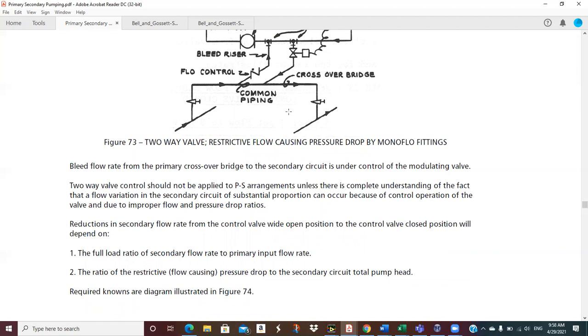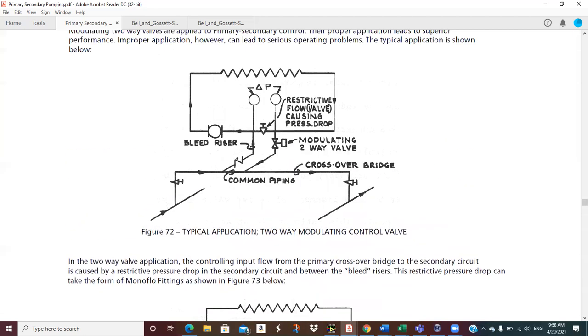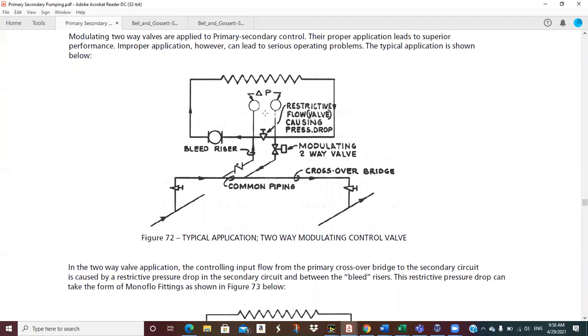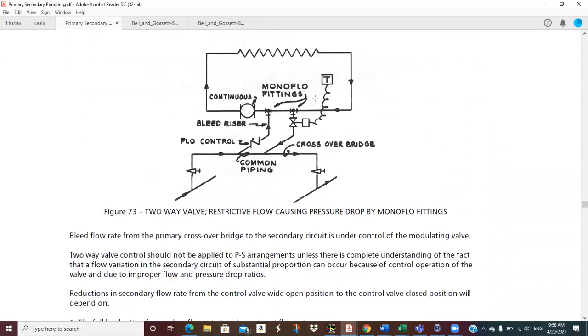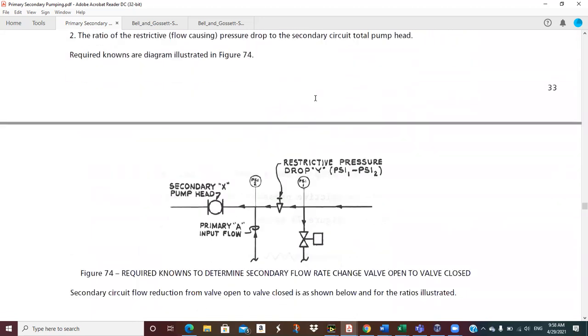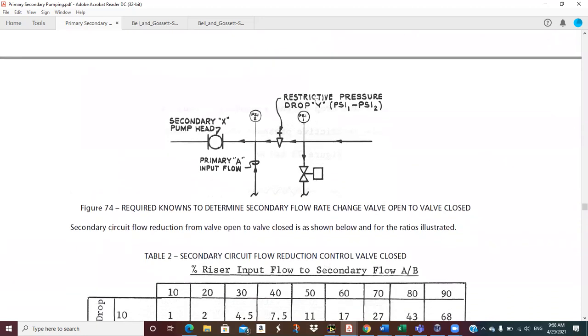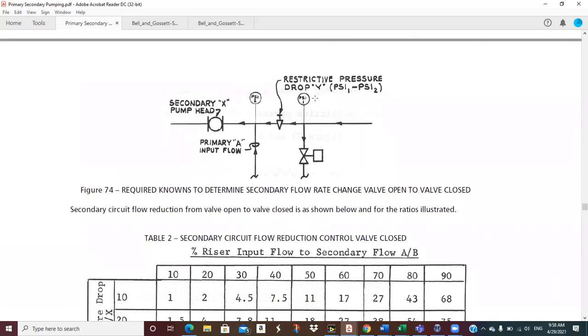And then the second thing is the ratio or the percent of the restrictive flow causing pressure drop in the secondary circuit to the total secondary circuit pump head. In other words, whatever this pressure drop is across here divided by the total drop for the entire secondary. And then the first one is the flow up through the bleed riser divided by the secondary flow rate. So to get this right, you have to calculate those, and they have to be within a certain range. And so he's just showing the diagram.